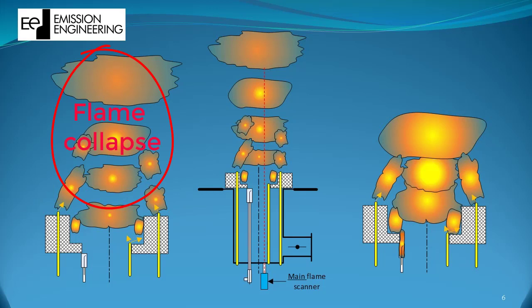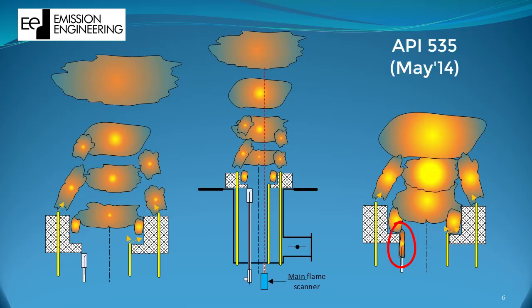In this case, you would need to have the main burner flame fully independent from what the pilot does, supervised by a dedicated flame detector for the main flame only. If your safety concept foresees not to have such main flame detector and you rely only on a continuous pilot, it of course assists the main burner to be relighted continuously. But keep in mind that as per API 535 May 14, it is clearly stated that the main burner must be reliably burning all fuels without a need for a continuous lit pilot.